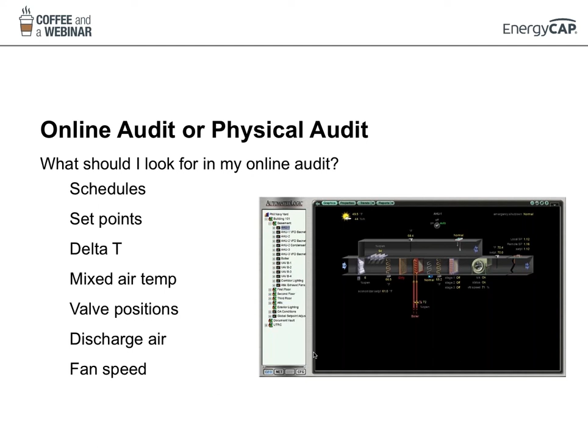So you're going through your online audit and physical audit, and these are the things you're looking for. You pull up your air handler unit, you're looking for schedules, set points. You want to make sure the delta T is right - if you have a very low or high delta T, there might be a problem. You want to make sure the mixed air temperature is good, that the outside air isn't bringing in too hot of air that's making you cool more or open your valve more to cool quicker. Valve positions, discharge air - these are all things you need to check weekly to make sure your building is working as designed.